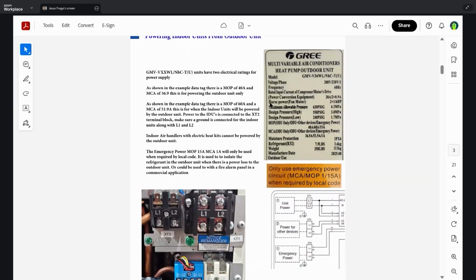So continuing on to the next page, this is what I was talking about, the capability of the outdoor unit to actually power the indoor units. There's a lot of information here that you'll need to follow when you want to utilize this XT3 terminal block. This XT3 terminal block is the one that is going to carry the power to the indoor units. And if this is utilized, as we see here on the nameplate, you will have to follow the MOP for utilizing the outdoor terminal block XT3. So that is 60 amps.